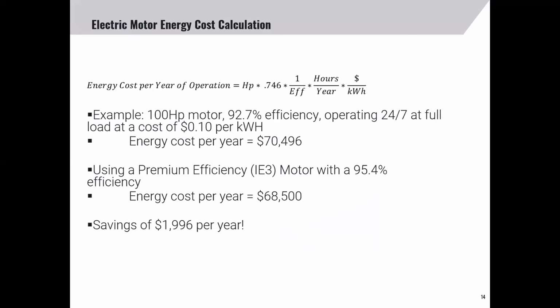But if you decided to use a premium efficiency motor, you can see the efficiency went from 92.7 to 95.4%. The energy cost per year is $68,000. So you have an annual savings of $1,996. But think about the actual cost and the life of that motor. A 100 horsepower motor can easily last 10 years. And if you're running that motor, that would put the cost of energy consumption over its life at over $600,000.